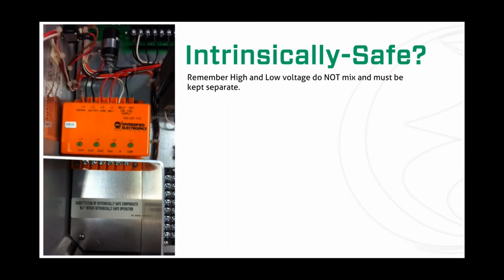Another big thing to remember is that high voltage, like going to your pump, and low voltage, in this particular case going to our float switches, do not mix. They must stay separated. According to the National Electric Code, or NEC, they must be separated. That's why you find this barrier that you can see here around this module, or where the wiring hooks up to this module. Just running your high voltage wires within a few inches of your low voltage wires can cause catastrophic failures. Again, this is very important. You should always run your high voltage wires, like I said, going to your pump, and your low voltage wires in situations like this in separate conduits. Running them together is never allowed and not recommended.